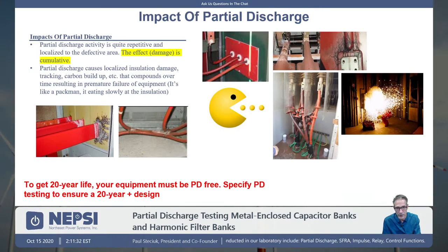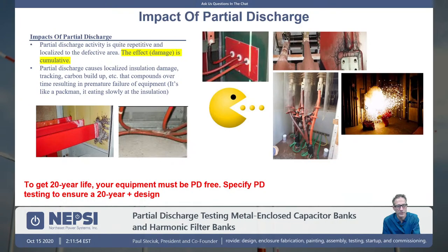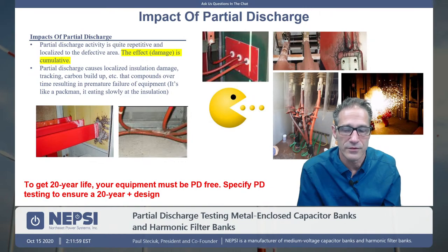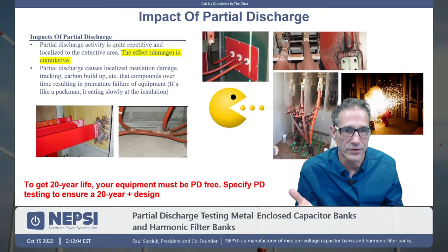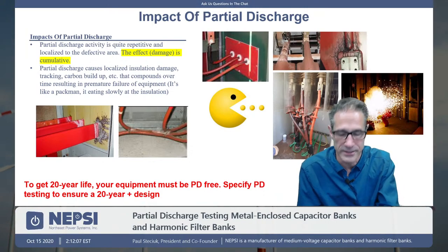One of the things to realize about partial discharge is that oftentimes the system will degrade over time. The insulation will crack, and it will become worse and worse. But it's the switching operation, that final voltage stress, the final voltage transient, that oftentimes results in an actual flashover, and that's what we see here. And it's an arc flash hazard situation. So NEPSI recommends that you look to do partial discharge testing and design your equipment to be partial discharge free. And that's really what this tech talk is about today.